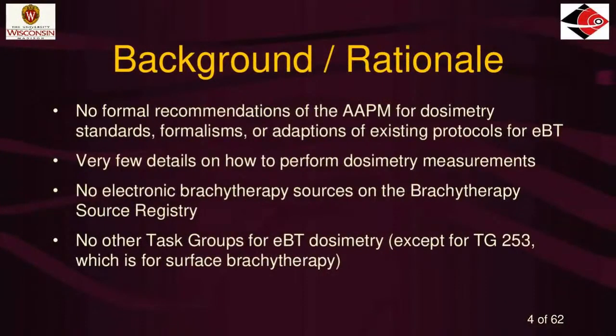No formal recommendations from the AAPM exist for EBT. There are three task groups in the works right now, but none of them are published yet. The other two are a little bit ahead of TG-292, which I'm involved in. There are very few details in the literature on how to do dosimetry measurements. There are no sources on the brachytherapy source registry, which is maintained by IROC Houston. If you're starting a brachytherapy program and want to make sure a source has been endorsed by the AAPM, you go to the brachytherapy source registry online. Right now there are no EBT sources on this registry — they're working their way on there, but not there yet. There is also no other task group specifically for EBT dosimetry.